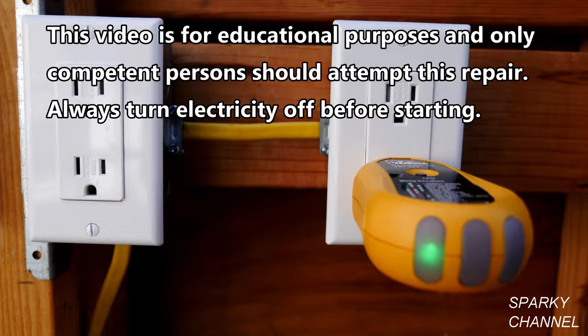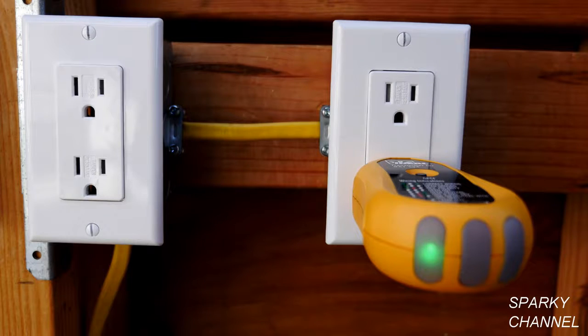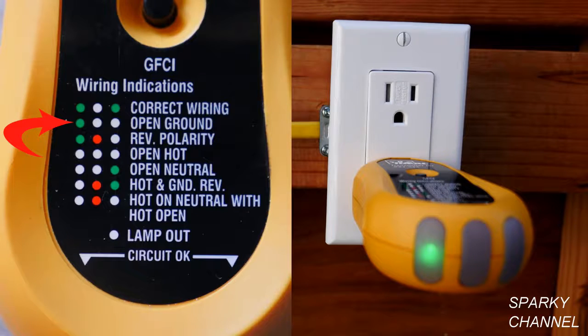Today I'm going to show you how to fix a receptacle that has an open ground. This means that this particular receptacle is not hooked up to the grounding system of the house. The first thing to do is plug in an outlet tester into the receptacle and notice what light pattern you get. In this case we get one green light on the left and then two blanks. And if you look on the index, one green light on the left and two blank lights is open ground. This means that this receptacle isn't hooked up to the grounding system of the house.